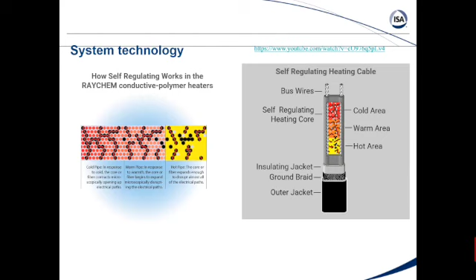And safety showers, obviously, being an important item of a plant, being a safety issue, people start thinking, okay, I'm going to put a self-regulating cable on there, and I'm not going to put any control on there, because if I put a control or a thermostat or something in there, that's another point of failure, and that could reduce reliability. So I'm just going to let it go, which is somewhat of a sound idea.